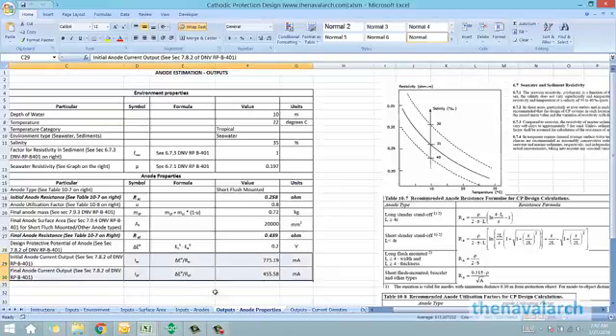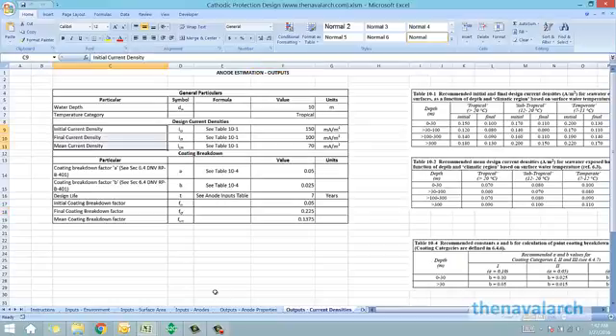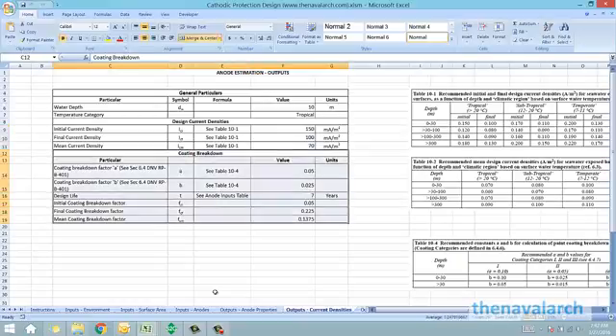Next is the output sheet on current densities. This is essentially the calculation of the current demand for cathodic protection. Based on the temperature category, depth of water, and coating category provided by the user, the spreadsheet calculates the initial, final, and mean current densities required for cathodic protection. It also calculates the coating breakdown factors used for final current demand estimation.